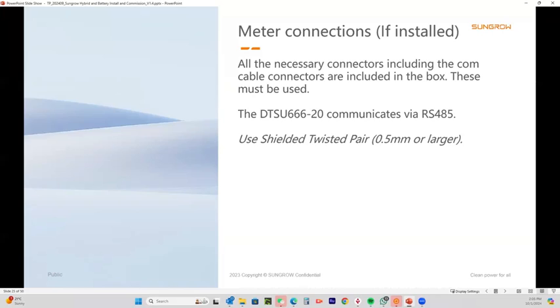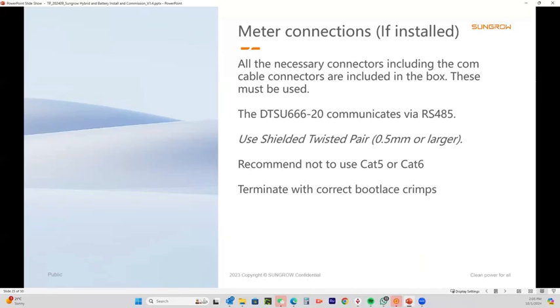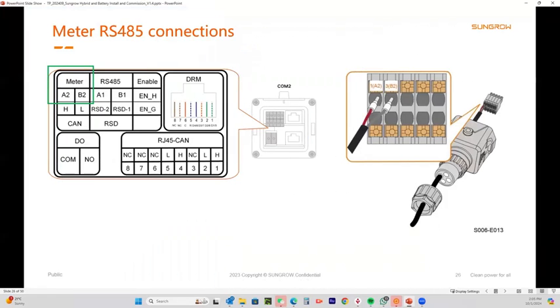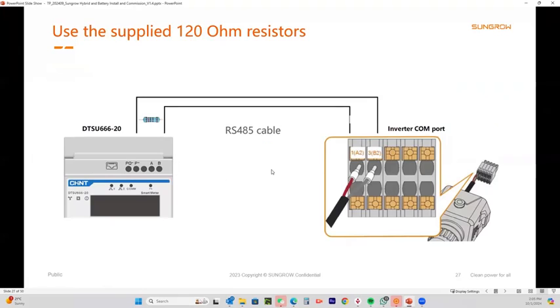RS485 is a 120 ohm impedance system, and the proper cable is rated at 120 ohms as well. So I recommend not to use the Cat5 or Cat6. If you do, well, it might work, but it might not. Terminate with the correct bootlace crimps, as I mentioned before. So the meter gets connected into meter A2B2 like so. A2B2 is marked A and B at the meter end, and A2B2 across all of our range. The meters always communicate on A2B2. You'll see RS485 A1B1, that is for inverter communications. Don't worry about that just yet. So here we are, A and B on the meter and A2B2 at the other end.